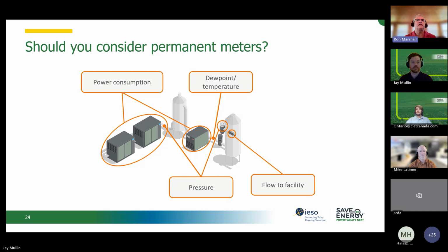having permanent metering that's electronic, that's feeding into a database is quite important for, say, troubleshooting, right? If you want to know the cause of that low pressure, you have to measure. So definitely pressure, before and after the dryers and filters is important. The power consumption or amp consumption of the compressors. Amps you can convert into kilowatts using some assumptions. Flow is quite important in my mind.